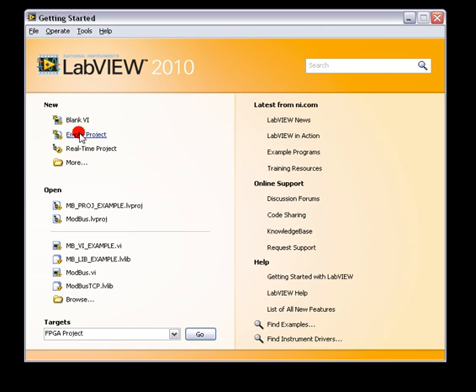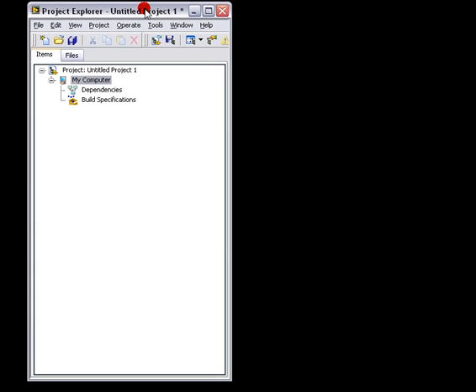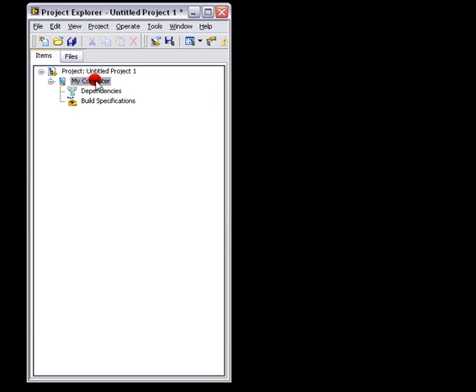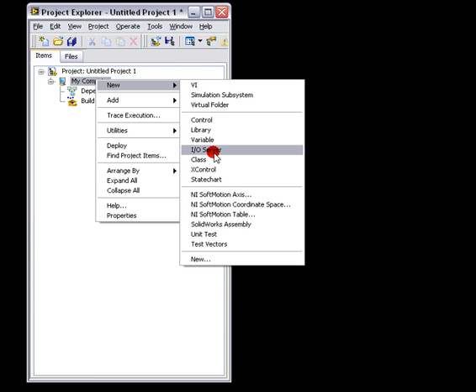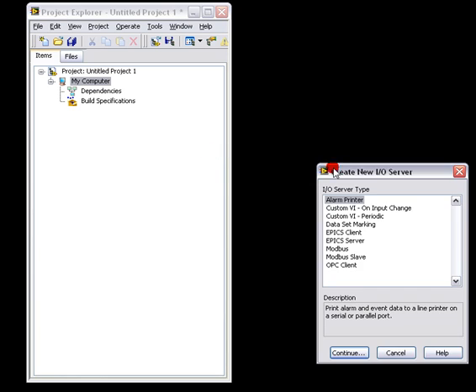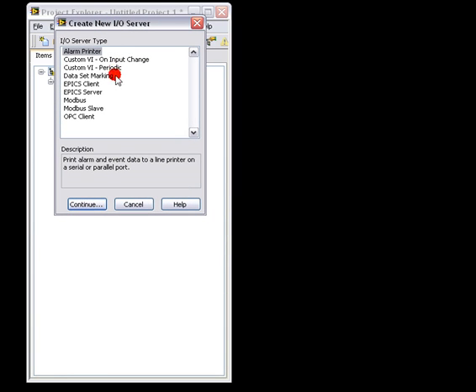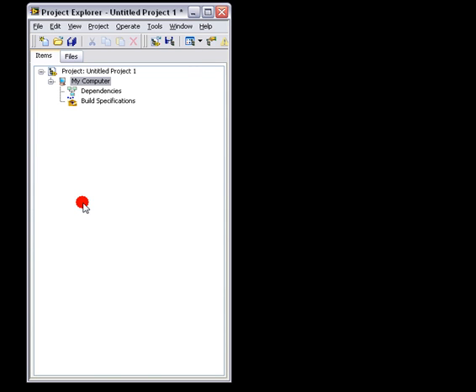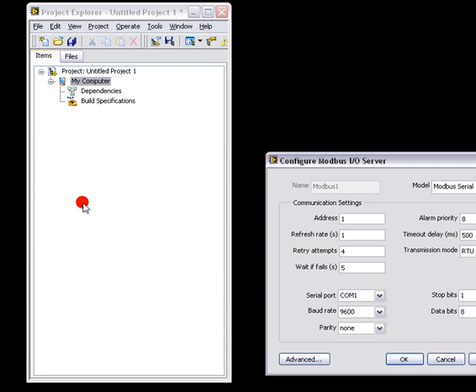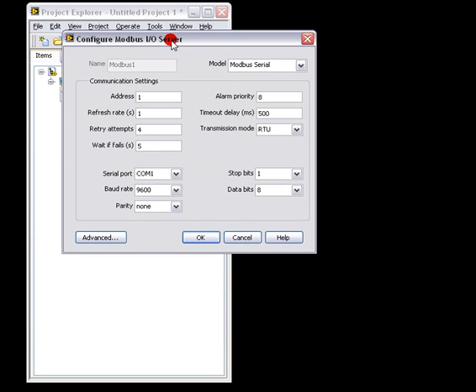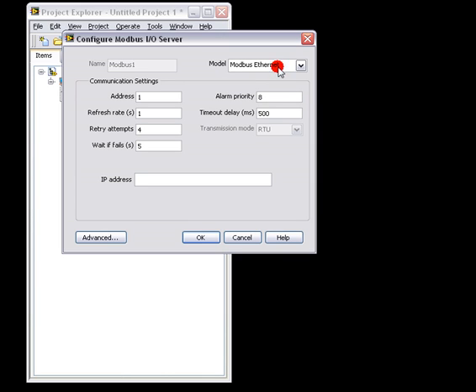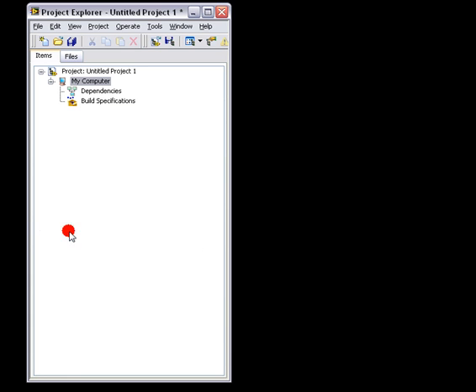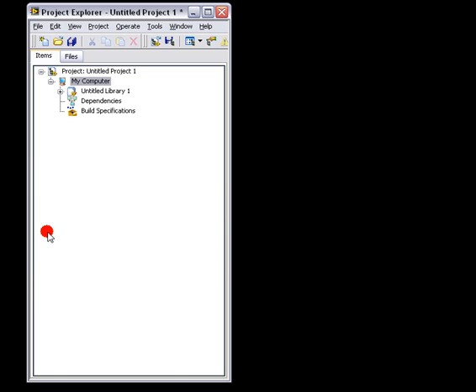We're going to just disconnect there, minimize that. And then we're going to launch LabVIEW 2010. We're going to need to create an empty project. And then we will create a new I.O. server here. And the I.O. server type will be Modbus. We want LabVIEW to act as a Modbus master. And then we will select that our connection is Modbus over Ethernet or Modbus TCP. Enter the IP address of our data logger. Select OK.